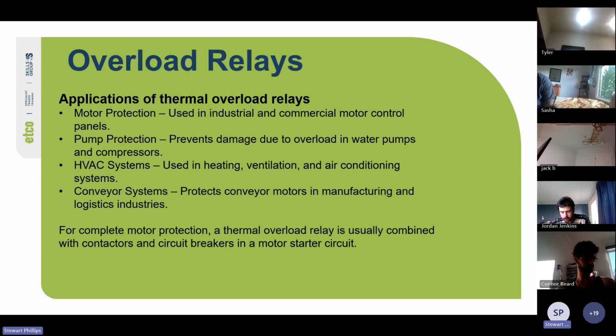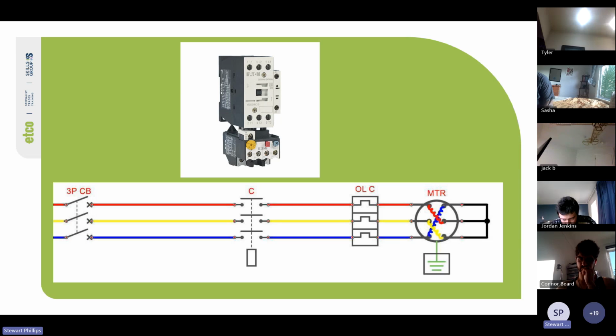For complete motor protection, a thermal overload relay is usually combined with contactors and circuit breakers in a motor starter circuit. So here you can see the contactor at the top with the thermal overload plugged into the bottom. For this particular contactor, the connection for the coil is mounted on the side, and below you can see the power circuit for a three-phase star connected motor. So you've got your three-phase circuit breaker, you've got your contactor with the coil C, and then you've got your overload for your contactor, or OLC, before your motor. So even though the power circuit is drawn with them separate like that, the physical connection is straight into the bottom of the contactor there.